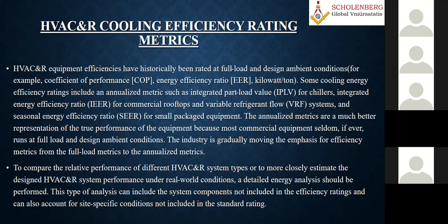Actually, this is another one. VRF system is also the latest one, which is now variable refrigerant flow. And then we also talk about the seasonal energy efficiency ratio for the small package plant. So the annualized metrics are a much better representation of the true performance of the equipment, because most commercial equipment is basically rated at full load. Everybody knows that, because we design for the peak ambient condition, but that hardly occurs in a year, a few days or a few hours.